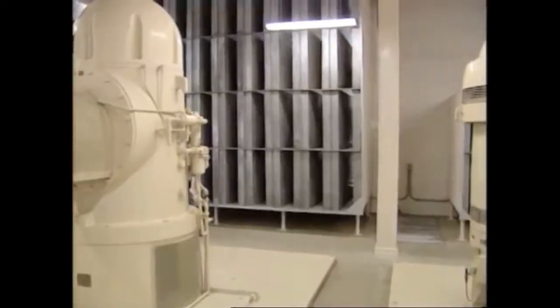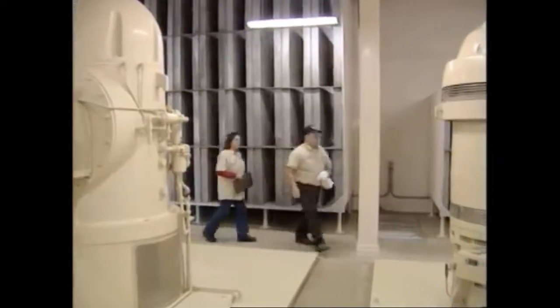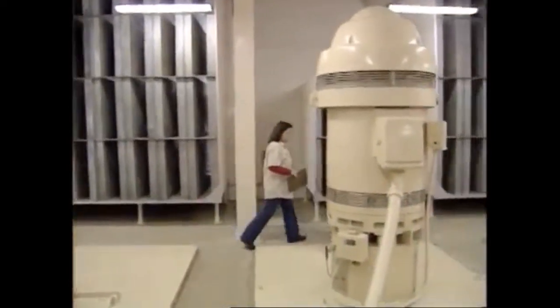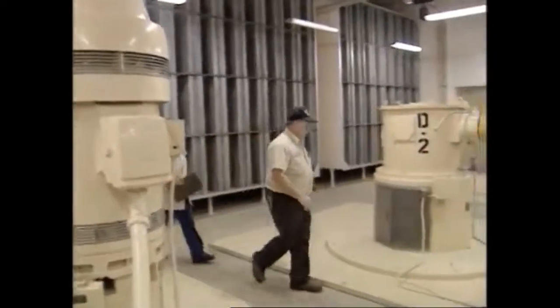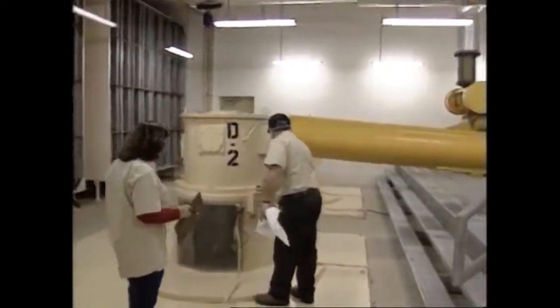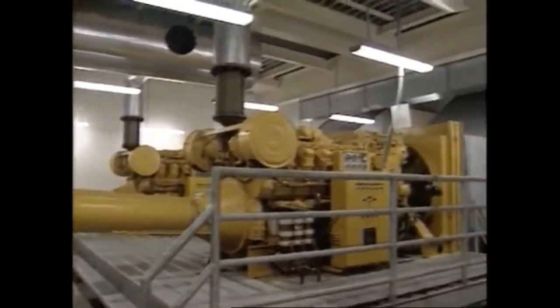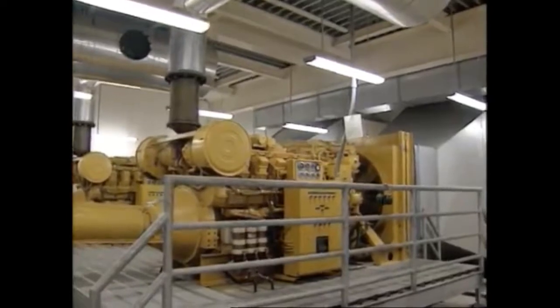Now let's talk about the efficient operation of a wastewater lift station. Lift stations and pump stations are used to lift or raise wastewater or stormwater from a lower elevation to a higher one. Lifting of the wastewater is accomplished by centrifugal pumps or air-operated pneumatic ejectors. A lift station such as this one pumps a relatively short distance into a gravity sewer. A pump station, on the other hand, pumps a relatively long distance into a force main.